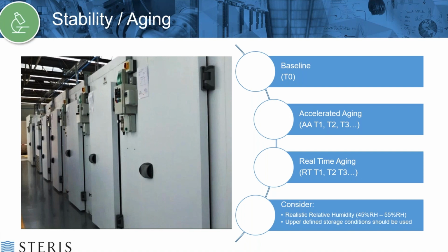So a couple things to consider. The ASTM standard for accelerated aging, F1980, now recommends using realistic relative humidity for your accelerated aging. Previously, it recommended using lower relative humidity, but since 2021, it recommends using 45 to 55% RH for your relative humidity. It does give you the caveat that you can define something else if you have data to support using a different relative humidity, but it does recommend using 45 to 55% RH at this point.